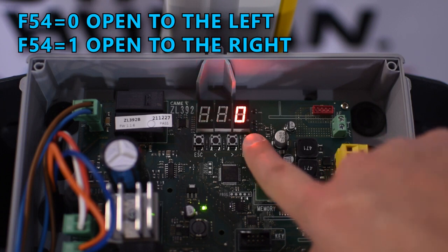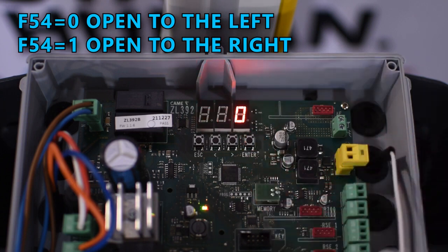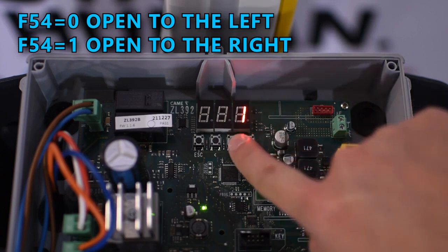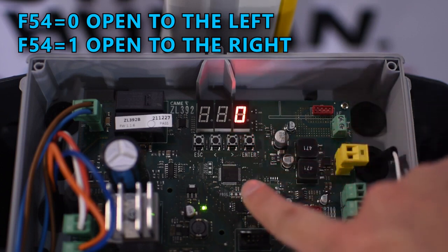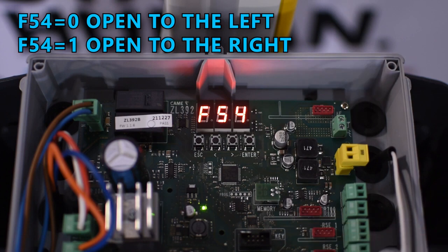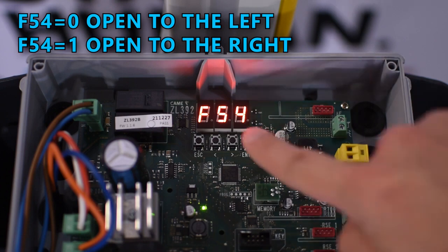If the barrier opens to the left, the value must be 0. Or if it opens to the right, you need to set it to 1. Go to F54 and select the corresponding value. In my case, it opens to the left, so I put it in 0. Remember to press Enter to confirm the selection.